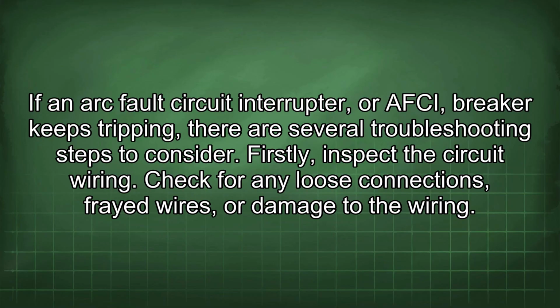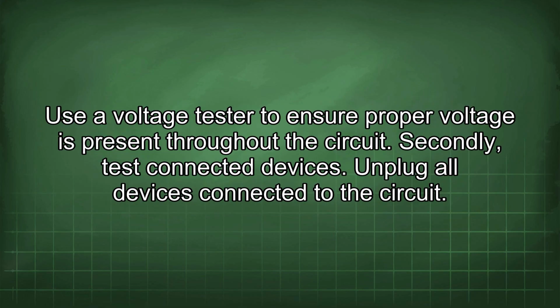If an arc fault circuit interrupter, or AFCI, breaker keeps tripping, there are several troubleshooting steps to consider. Firstly, inspect the circuit wiring. Check for any loose connections, frayed wires, or damage to the wiring. Use a voltage tester to ensure proper voltage is present throughout the circuit.